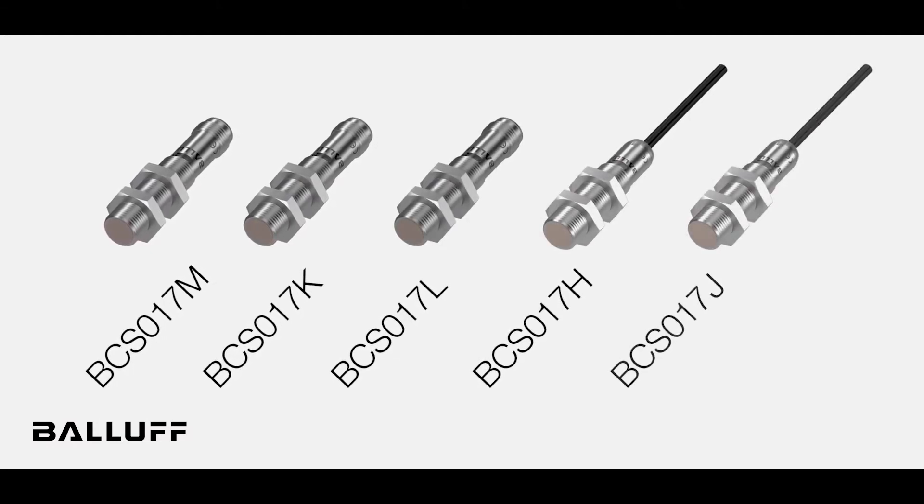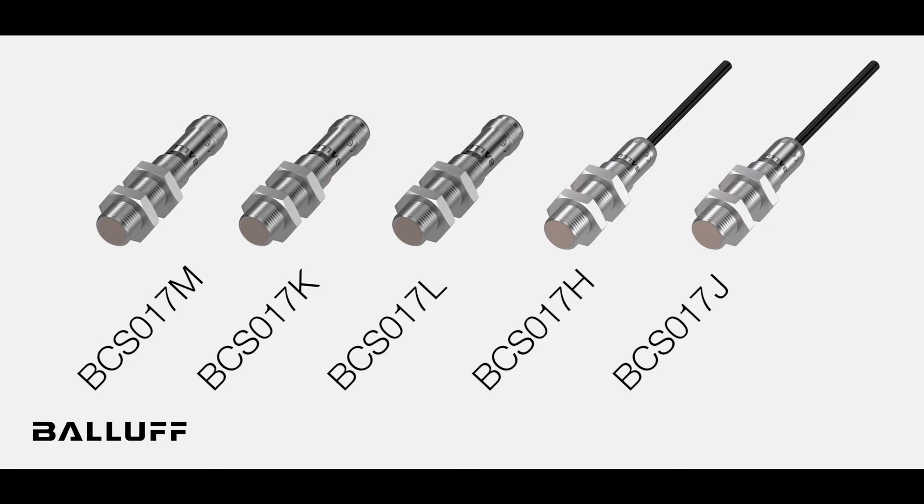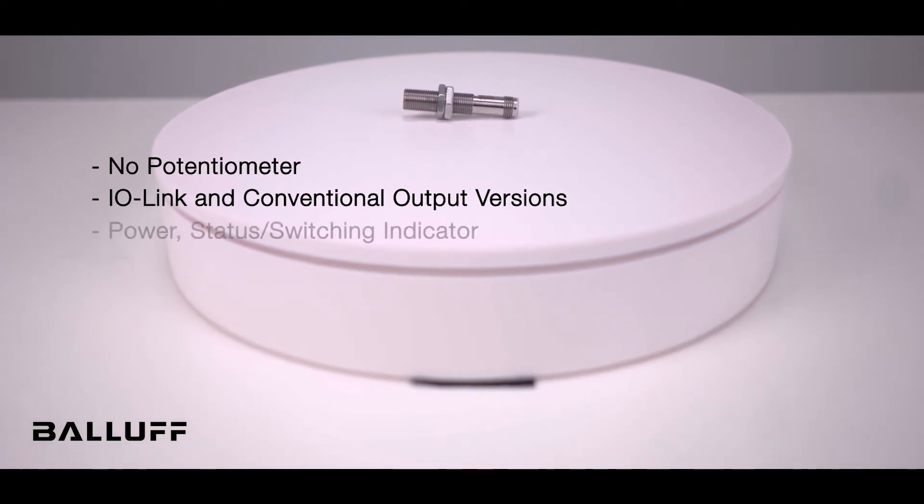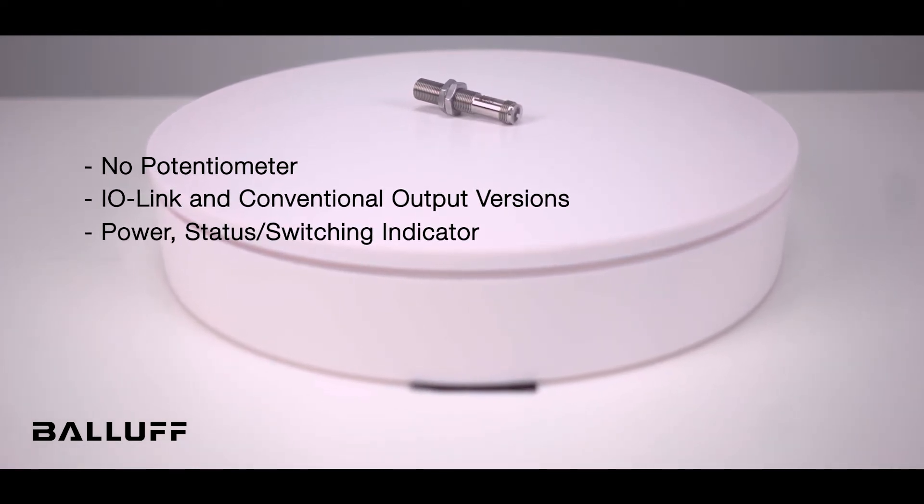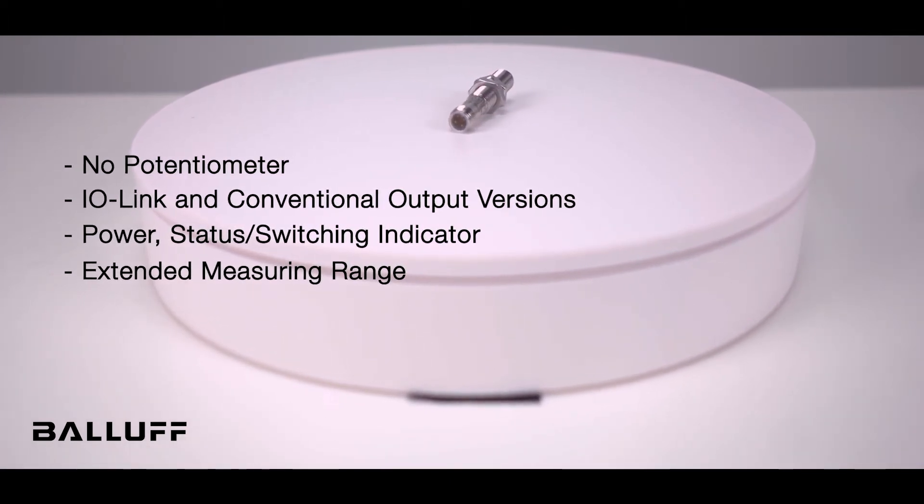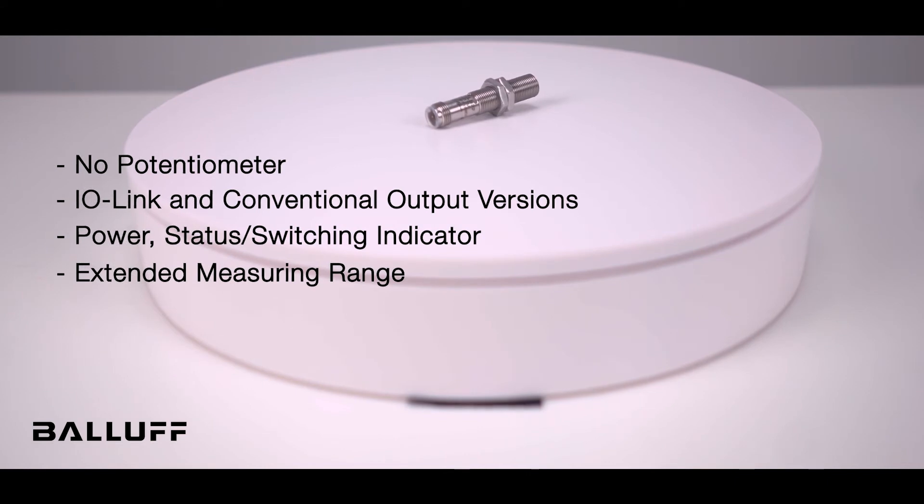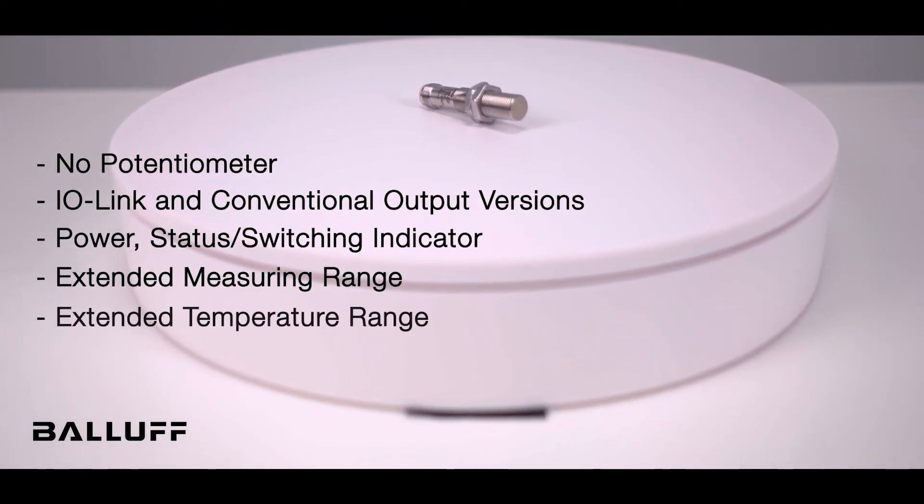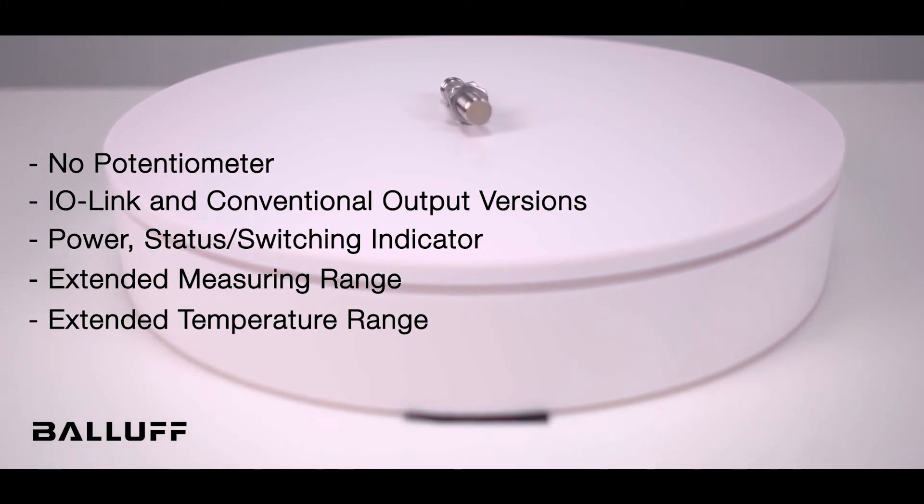Our newest versions, the BCS017M K, L, H, and J, offer optimized technical features including no potentiometer, IO-Link and conventional output versions, power, status, and switching indicators, extended measuring ranges from 0.5 to 5 mm for object detection and 0.5 to 8 mm for level detection, and extended temperature ranges of negative 10 to 80 degrees Celsius.